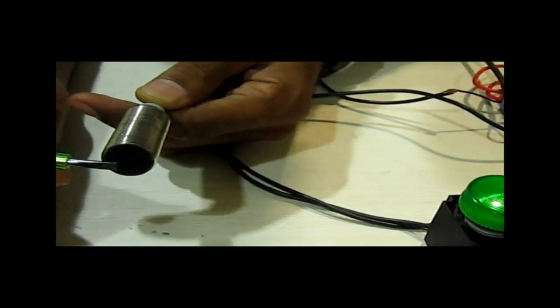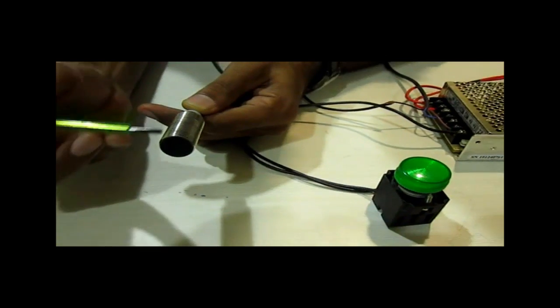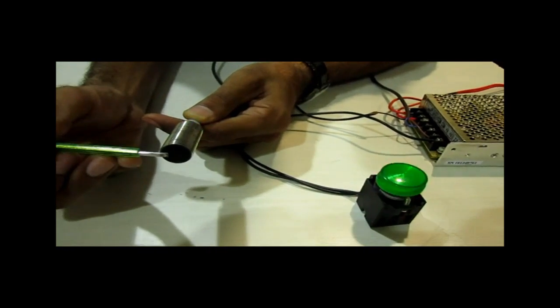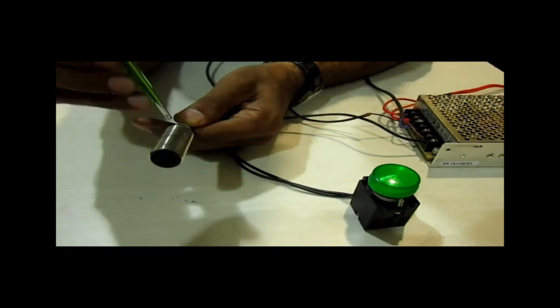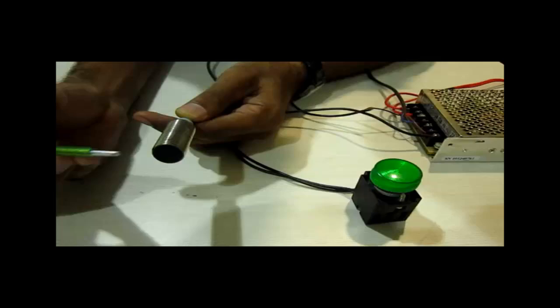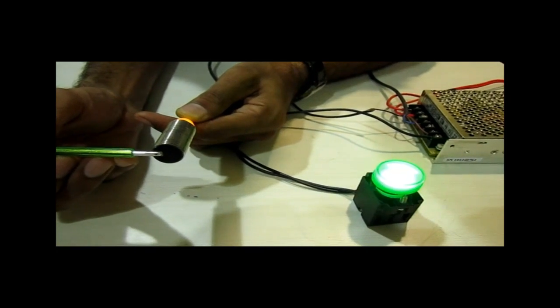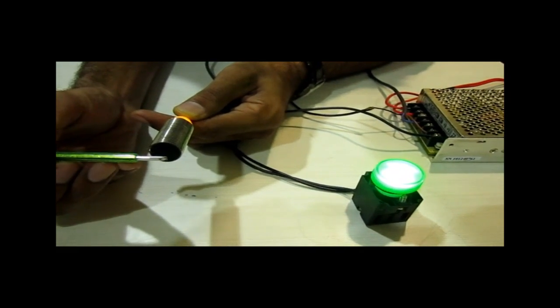These induced eddy currents affect the magnetic field because there are some losses in that case. These losses are detected by the circuit inside the sensor, which gives indication that some metallic object is in the magnetic field area. That's how it works.